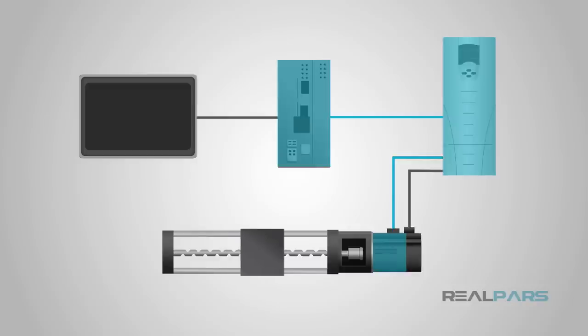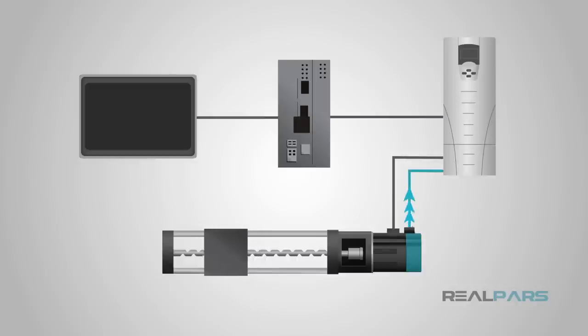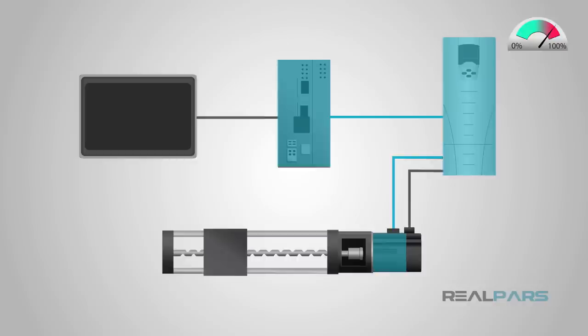This error correction is accomplished for servo motor torque, velocity, and/or position. In addition, servo drives have the added advantage of including a position fault error limit. If the position error feedback by the encoder exceeds a limit, the servo motor controller will fault the motor, thereby preventing any erratic movement that could lead to potential damage to equipment, product, or people. The positioning error fault limit can be adjustable, allowing for tighter and better defined control.